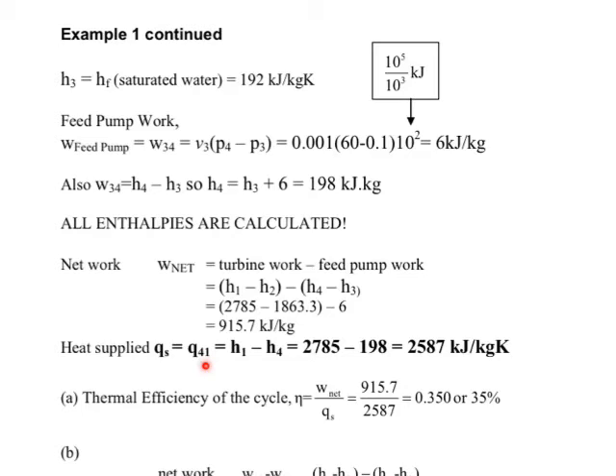The heat from point 1, remember that is at the turbine inlet, we are assuming no losses between the boiler output and the turbine inlet, minus H4 which is the enthalpy immediately after compressing the condensed steam from 0.1 bar to 60 bar. And so we have H1 minus H4, 198 and we get 2,587 kilojoules per kilogram K.